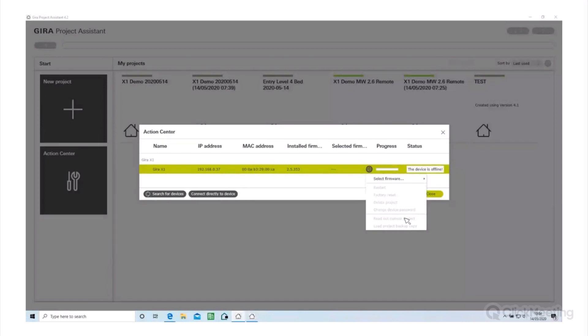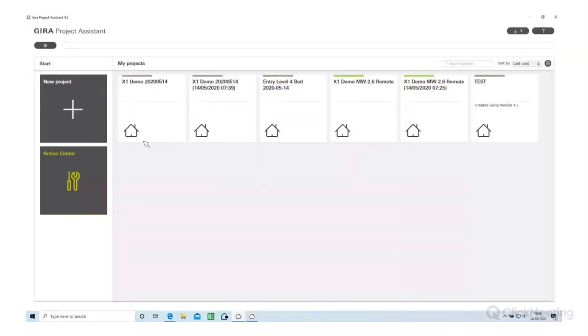When you open a project from file, make changes, do the commissioning and download, it will ask if you want to load the customizations from the project back up. There is a known issue being fixed in a future release - if you've made changes to a project that isn't the one on the device and then download, the information can end up out of sync. The recommendation is to read out the current project first, make changes to that, then download so it syncs correctly.